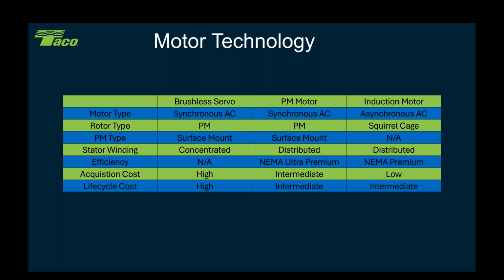So what happens is on a permanent magnet motor, I have to have a VFD on a permanent magnet motor. With a permanent magnet motor, I cannot hook that up and run it across the line like I can with an induction motor, okay? So we have to understand that.